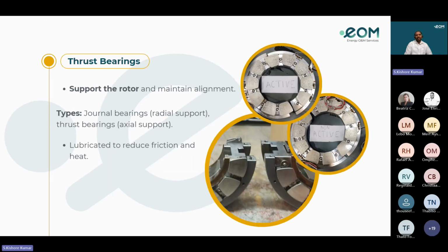Coming to the thrust bearings. Thrust bearings play a critical role in turbines by supporting axial loads, that is, forces that act along the shaft axis. Thrust bearings prevent the rotor from shifting axially, ensuring proper alignment and safe operation of the turbine. They absorb axial thrust loads, maintain the rotor alignment, and protect against mechanical contact. Here we can see the tilting pad active and non-active thrust bearings.